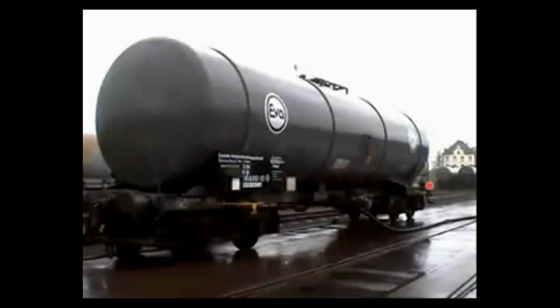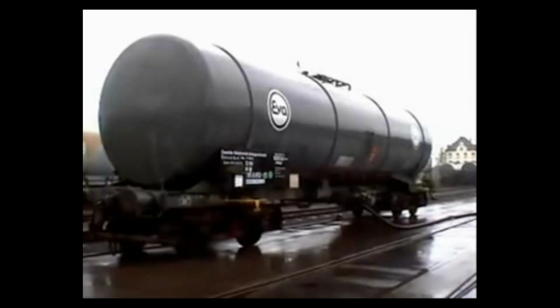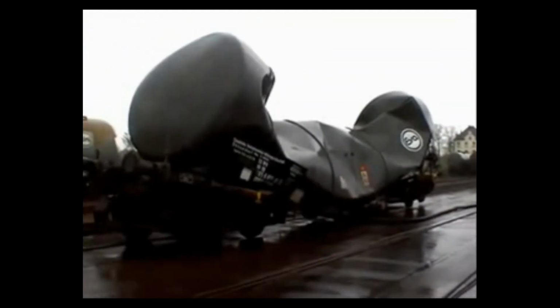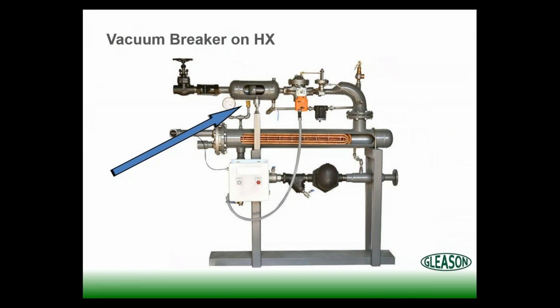This next slide is just a demonstration of vacuum. They've got their steam hose coming into the tank car, and they've disabled the vacuum breaker, and the steam is going to condense. So that's a little overly dramatic. We have seen the after effect of that. So let's put a vacuum breaker on our shell and tube, or actually any steam heat exchanger.